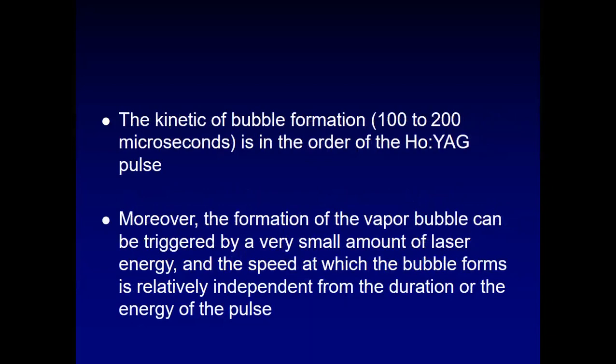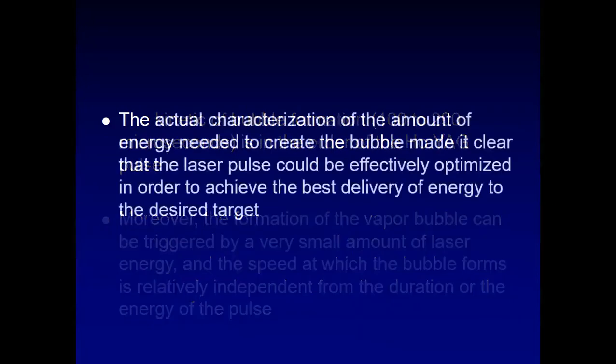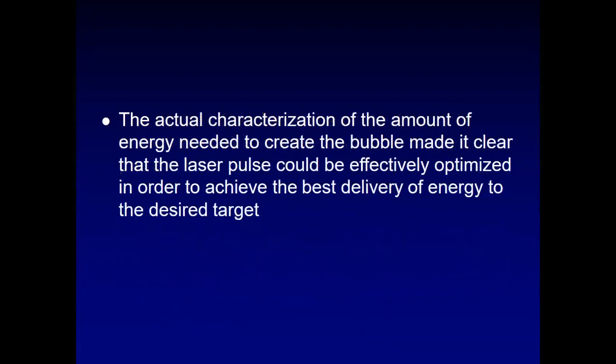The kinetics of bubble formation is 100 to 200 microseconds, and in order for the YAG laser to perform the pulse, you will understand this concept after these slides, 2-3 slides. I'll show you a video, and then you will get the concept of what goes on. The formation of a water bubble can be triggered by a very small amount of laser energy, and the speed at which the bubble forms is relatively independent of the duration or the energy of the pulse. The actual characterization of the amount of energy needed to create the bubble made it clear that the laser pulse could be effectively optimized in order to achieve the best delivery of energy to the target tissue.